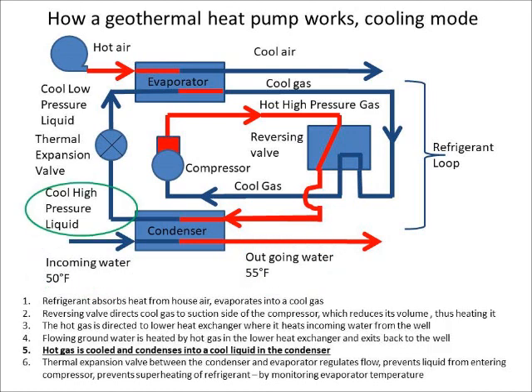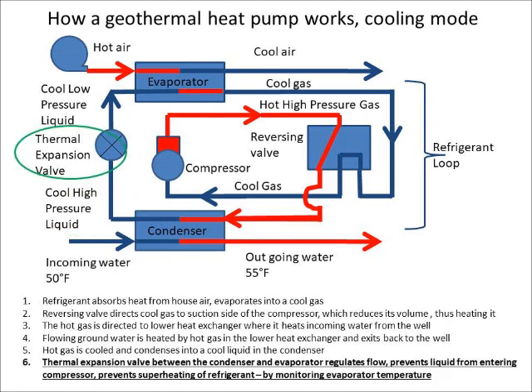Fifth, the hot gas is cooled and condenses into a cool, high-pressure liquid in the condenser. Sixth, the thermal expansion valve allows the cool, high-pressure liquid to expand into a cool, low-pressure liquid and regulates the flow between the condenser and evaporator. It prevents liquid from entering the compressor, and it prevents superheating of the refrigerant by monitoring the evaporator temperature.